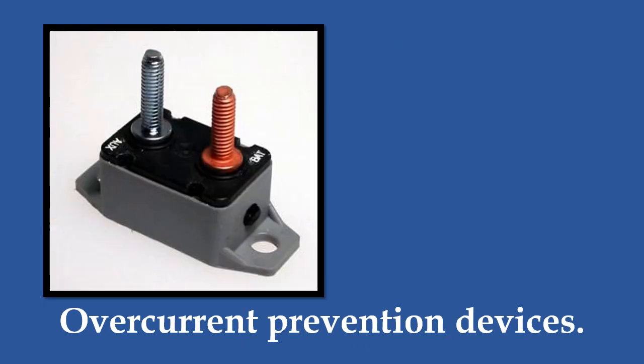Another inline overcurrent device is the automotive type circuit breaker. This type of automotive circuit breaker is housed in a sealed plastic body. This specific overcurrent device has a manual reset. The reset button can be seen on the right side of the breaker. If this device senses an overcurrent, it will trip and stop current flow to the downstream conductors on that circuit. With this device, current will only be restored when the reset button is pressed.